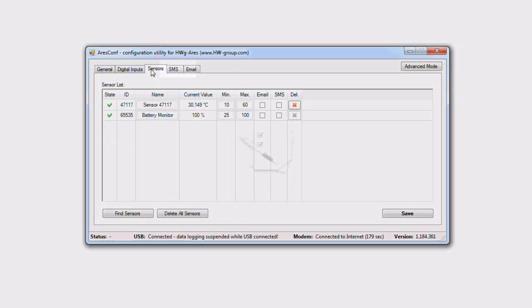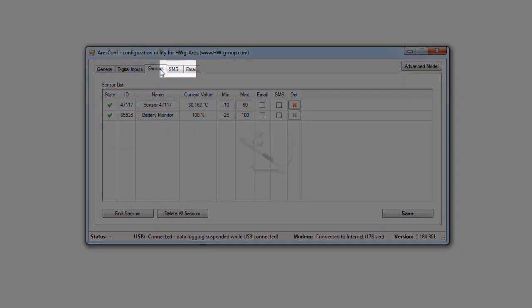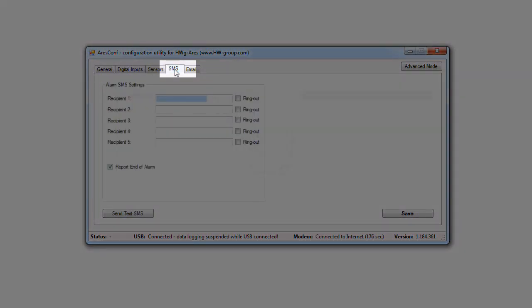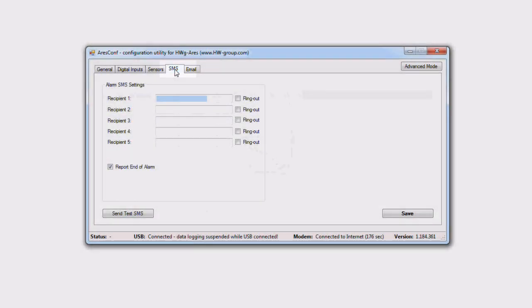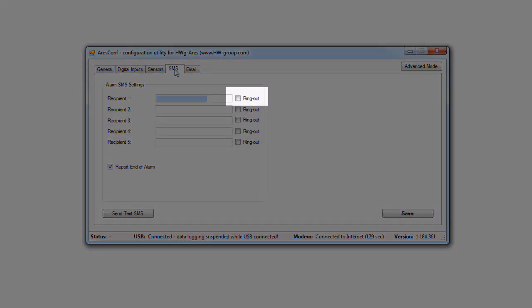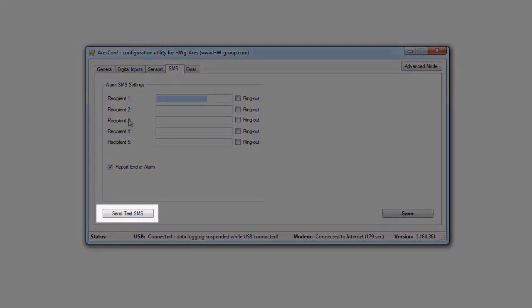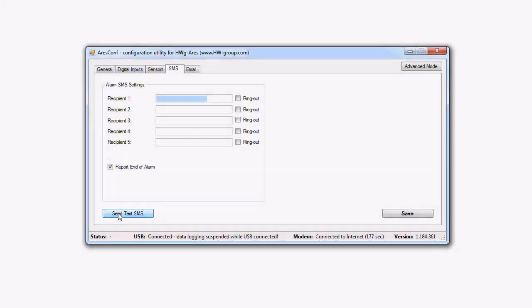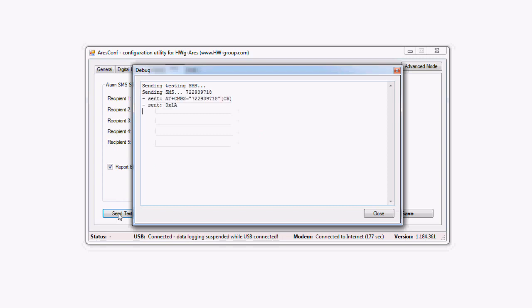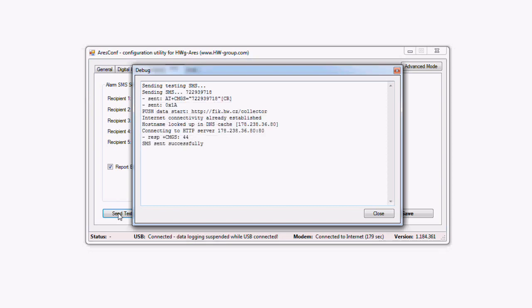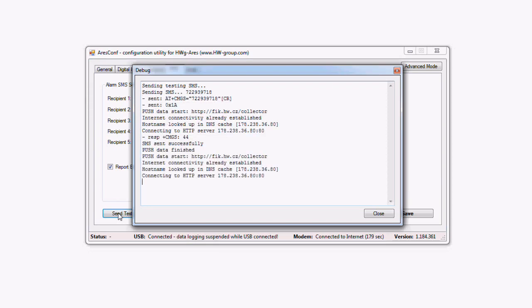In the SMS tab, it's possible to insert phone numbers for sending alarm SMS. At the same time, you can set if this phone number will be drop called. It means that the start and end of alarm will be reported by a drop call lasting 15 seconds. You can verify the function by pushing the send test SMS button. To save time, we test only the SMS and not the drop call.